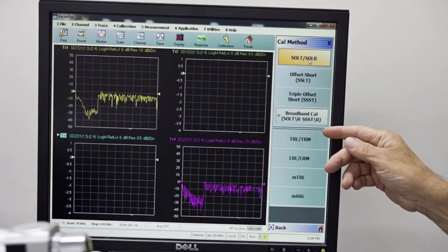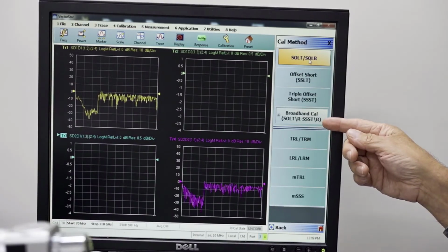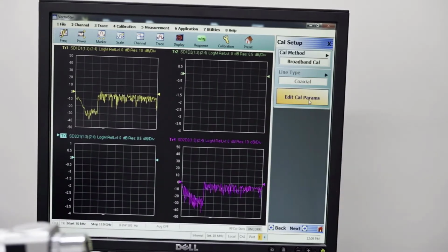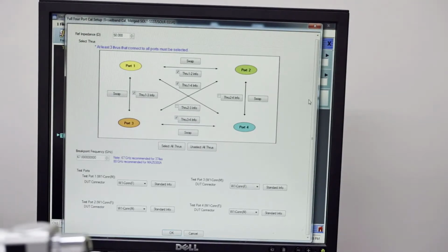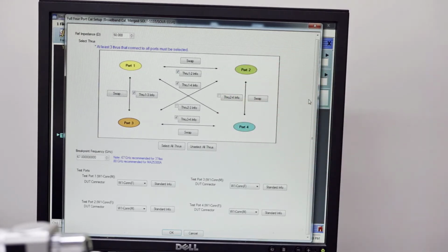And so that uses SOLT and then triple offset short for the millimeter wave frequencies. The final configuration step would be to edit the cal parameters. And so this is where we would designate the throughs that we are going to use. And so there's many different variations and selections available of the through pairings based on what is appropriate for your calibration. So in other words, in some cases for on-wafer measurements, there's a limitation on some of the through paths, and so you want to choose the paths that make sense or are achievable for the configuration.